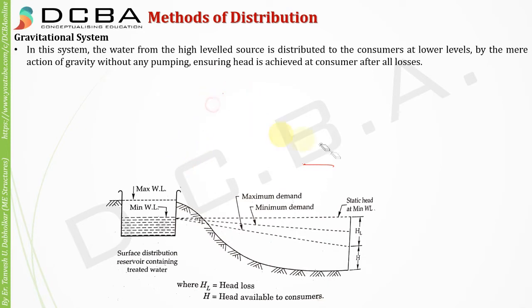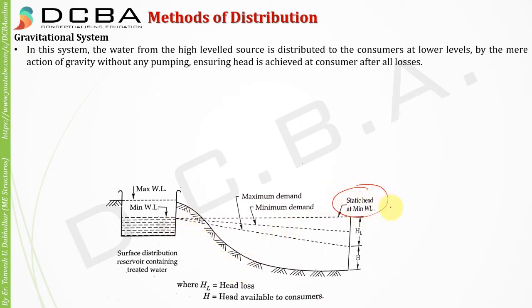For this purpose the treatment plant should also be located above the city. From the treatment plant, water is stored into a distribution reservoir, which should be above the city, and from there it flows to consumers by gravitational force. When water flows through pipes there is head loss. If head loss is not considered, the head generated by that flow is called static head — that is, without any head loss.